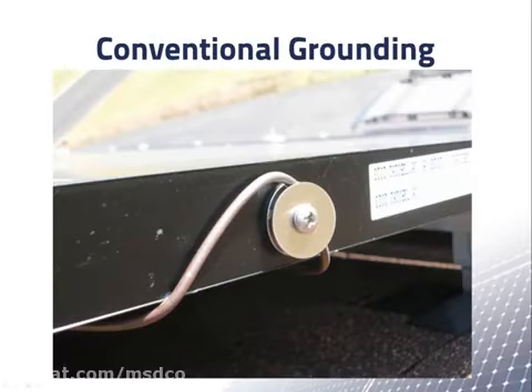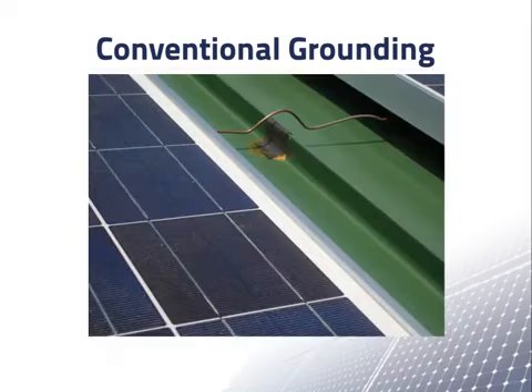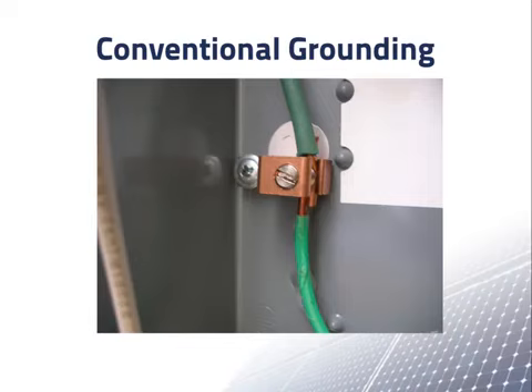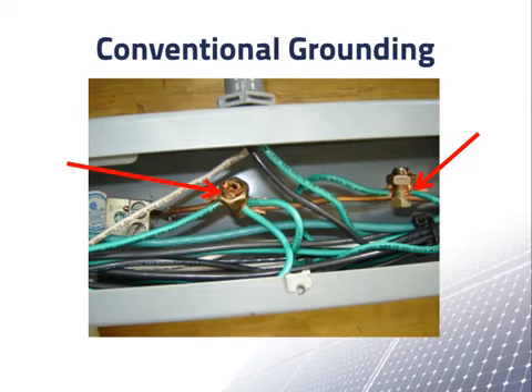There are at least two mistakes here. First, you can't simply use normal bolts and washers for a grounding connection. You need to use equipment that is listed for grounding connections. Second, we see that the copper comes into direct contact with the aluminum, which will eventually cause galvanic corrosion. In this case, the wire stays above contact with the metal roof below it, but someone working on the roof could easily trip on it. This grounding lug is listed for only having one wire connected to it, but it has two. Remember, it is a code violation to use equipment in a way other than what the manufacturer intended. In this picture, we see two places where a connector intended for 2 wires is being used for 3 wires.